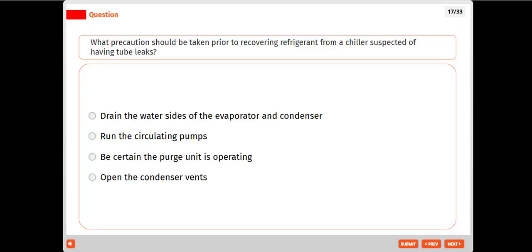What precautions should be taken prior to recovering a refrigerant from a chiller suspected of having a tube leak? Drain the water sides of evaporator and condenser. Run the circulating pump. Be certain the purge unit is operating. Open condenser vents.